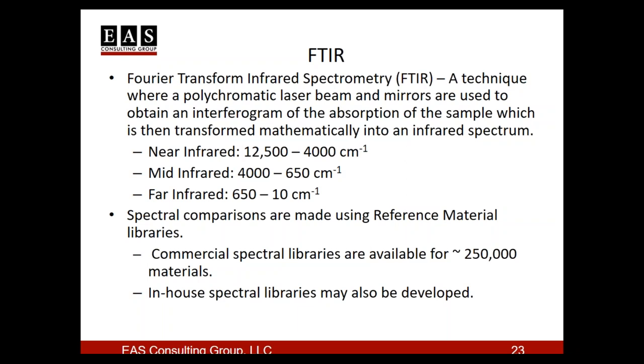There are a couple of different ranges where that can be done. Most common is the mid-infrared, 4,000 to 650 inverse centimeters, versus the near-infrared, which has also become more popular recently, beyond that at 4,000 to 12,500. Again, we obtain this spectra and compare it to a reference material library. There are commercial libraries available with something like 250,000 different types of materials, or you raise them in-house. The key is that reference material has to be characterized ahead of time to make sure it's appropriately identified.